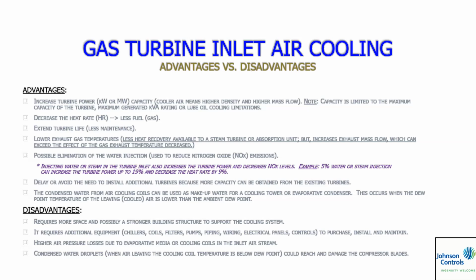Higher air pressure drops due to evaporative media or cooling coils in the inlet airstream. That is true. Okay. We have to design the system so that the pressure drop through those coils is pretty low, which means we make sure the face velocity through the coils is low, because the lower the face velocity, the lower the pressure drop. Just like if you're sizing a regular air handling unit, same thing. Instead of 500 feet per minute through the coil or 600 feet per minute through the coil, you get moisture carryover and high pressure drop. You make the coil a little bigger, more face area, reduce face velocity.